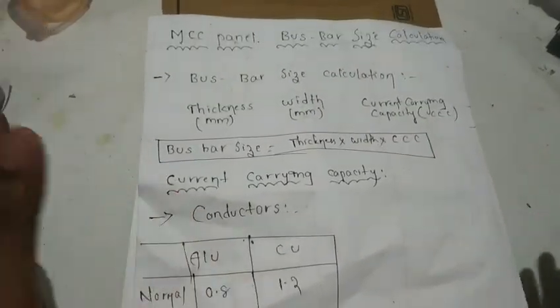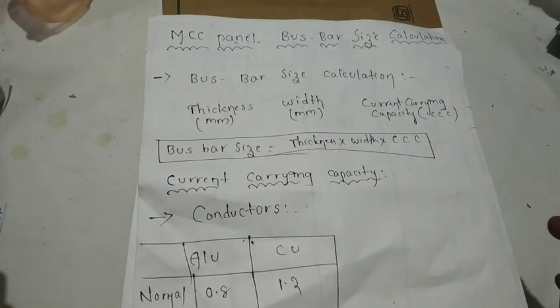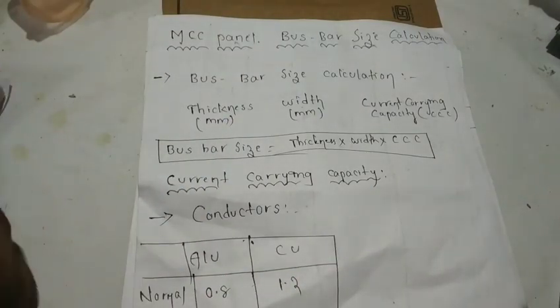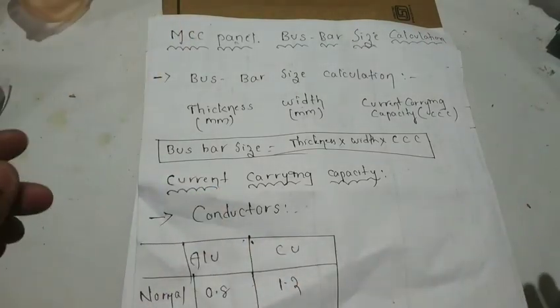Hello friends! Now we are going to talk about MCC Panel Bus Bar Size Calculation. This bus bar can be calculated as well. So I have 900 amps. Then you have the size of the bus bar, the thickness of the bus bar, and the width of the bus bar. What type of bus bar - this is aluminium bus bar, copper bus bar - and the current rating value. I will calculate the thickness.